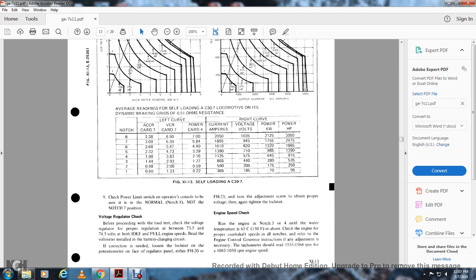Check the power limit switch on the operator console; be sure it is in the normal notch 8, not notch 7 position. Voltage regulator check. Before proceeding with the load test, check the voltage regulator for proper regulation between 73.5 and 74.5 volts, both at idle and full engine speed. Read the voltmeter on the battery charging circuit. If correction is needed, loosen the lock nut on the potentiometer on the regulator panel, either FH20 or FH23, turn the adjusting screw to obtain the proper voltage, then tighten the lock nut again.